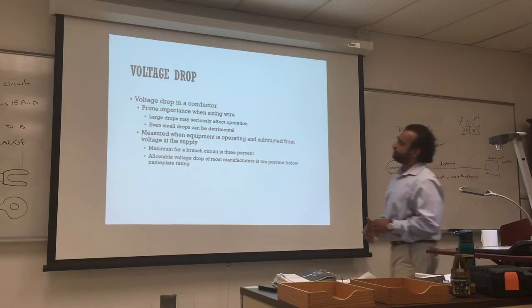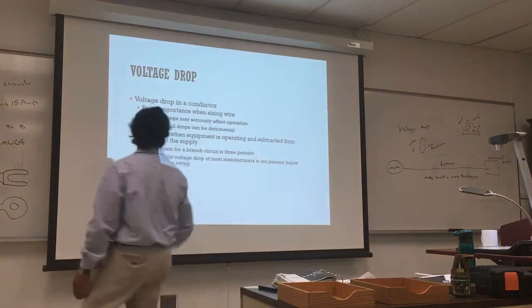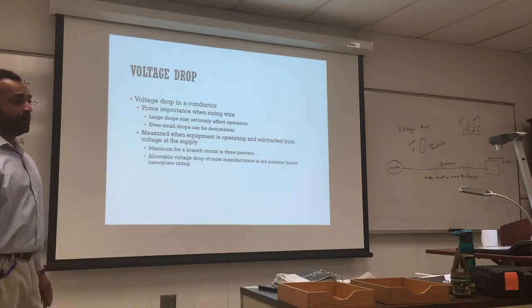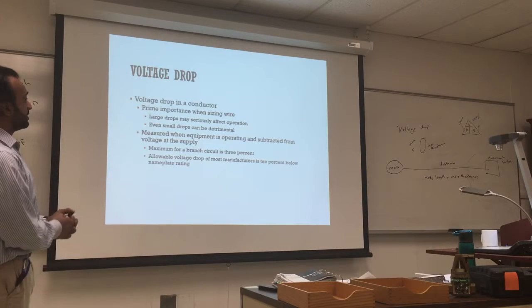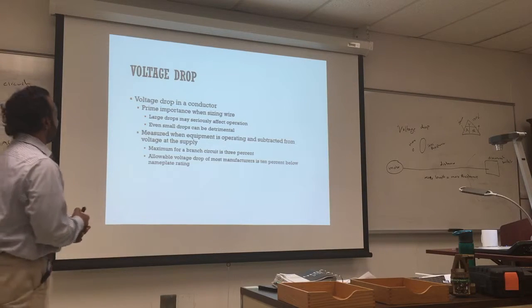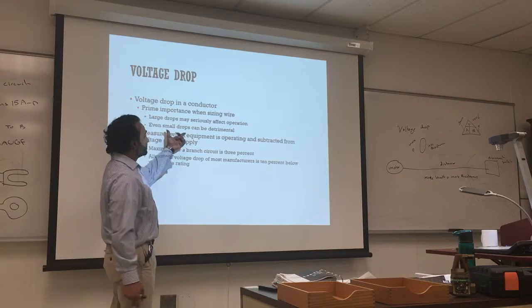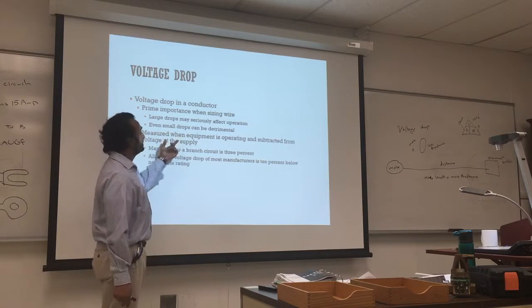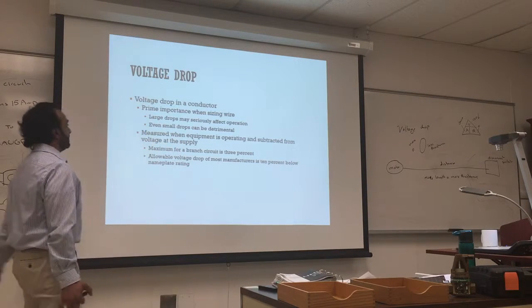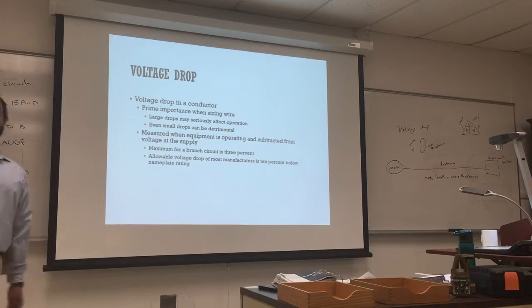Voltage drop in a conductor is prime important when we do wiring sizing. We wish to make sure we did not drop the voltage by too much. Even small drops, like 10%, can be an issue for things not running correctly, and that's something you have to think about.